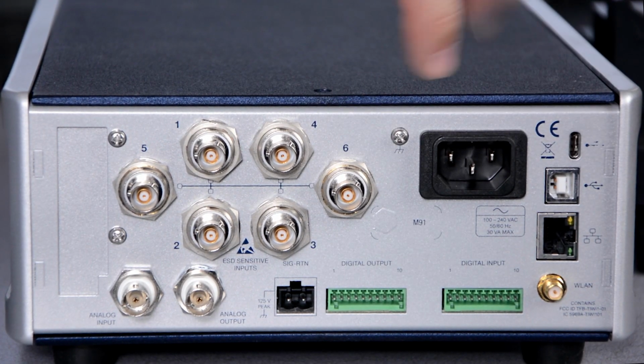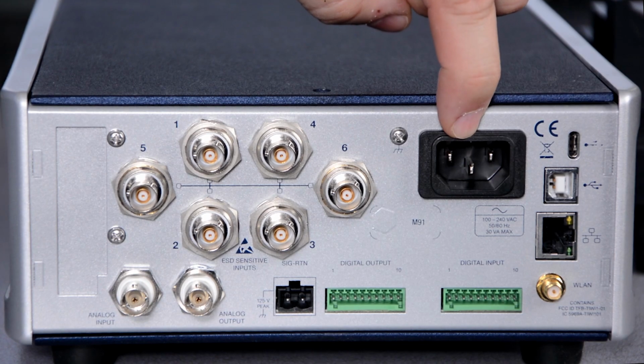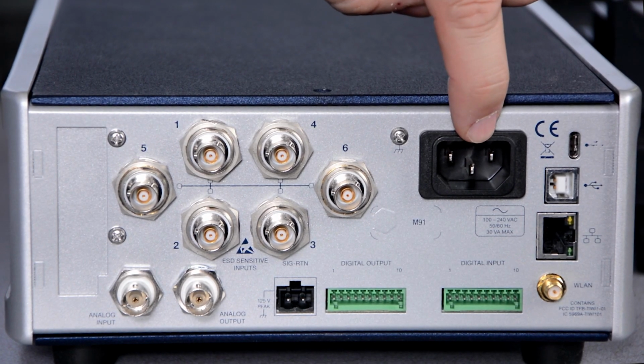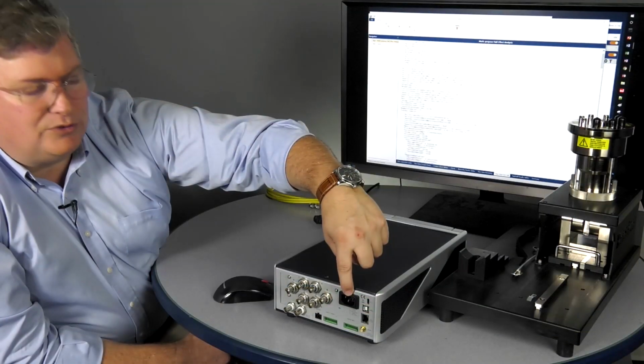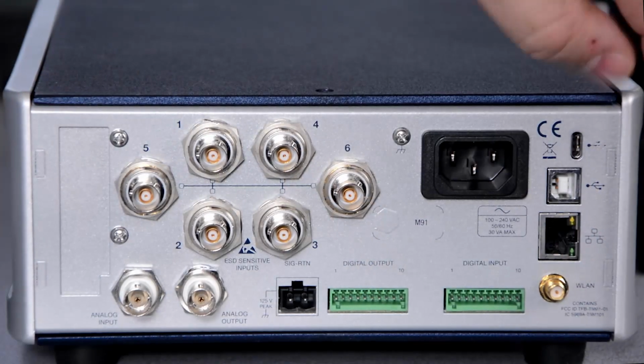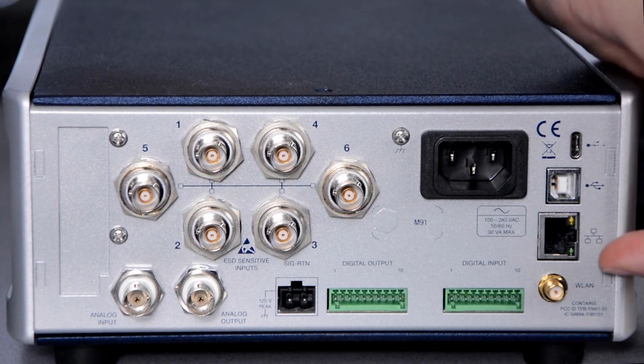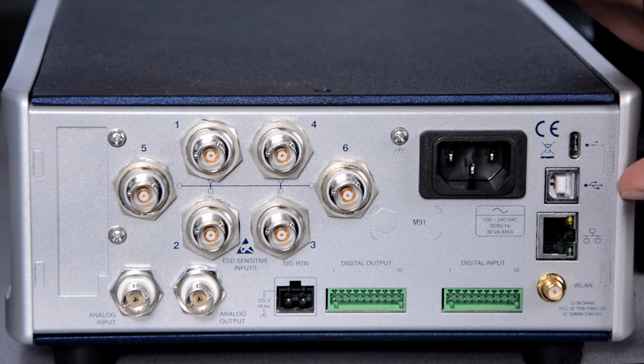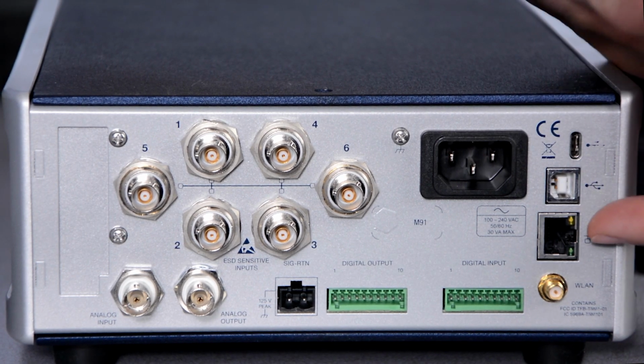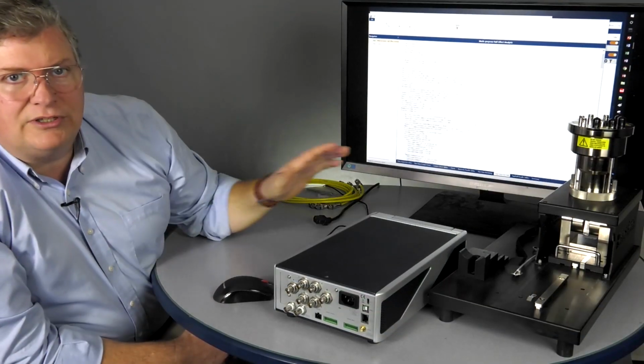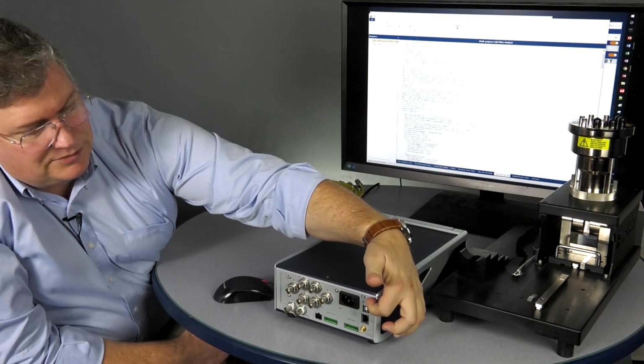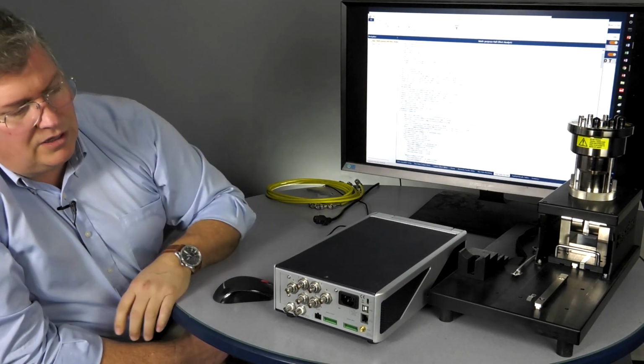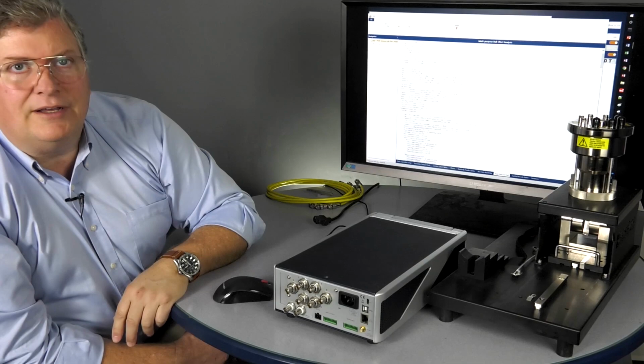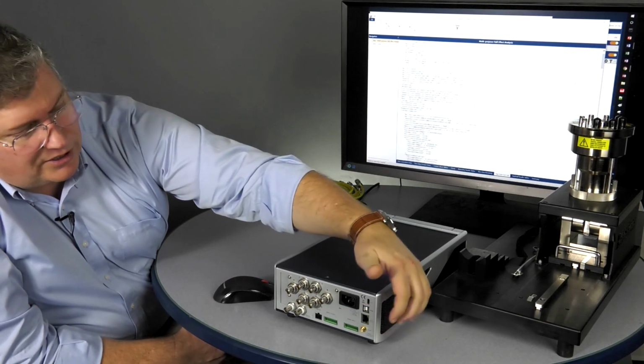On the power side, we have a universal input power supply, so the mains coming in are between 100 and 240 VAC. We have two communication connections. We have a USB-B connection or an Ethernet connection for going to the computer. And then we also have a USB-C connection to help us pull data off with, say, a thumb drive.